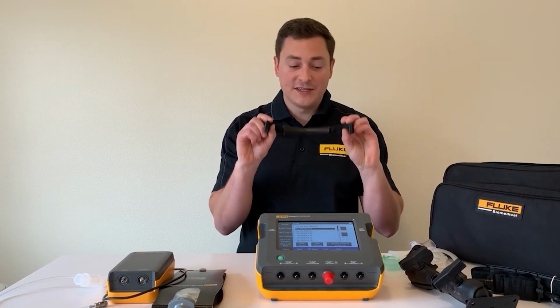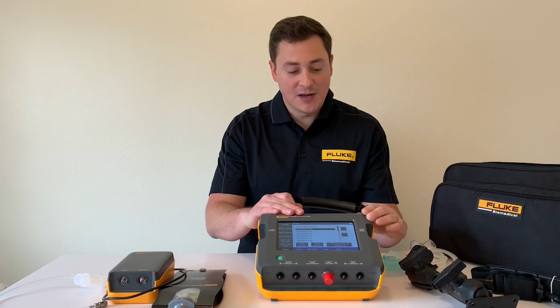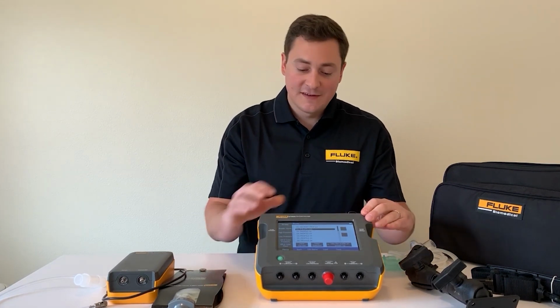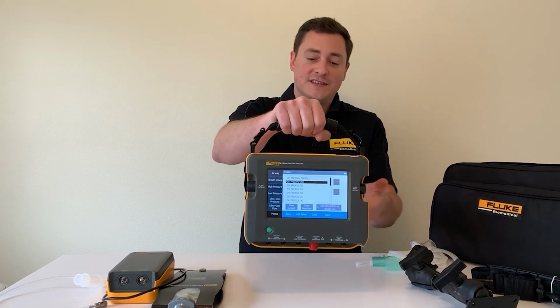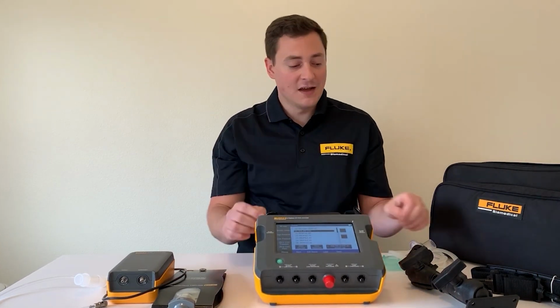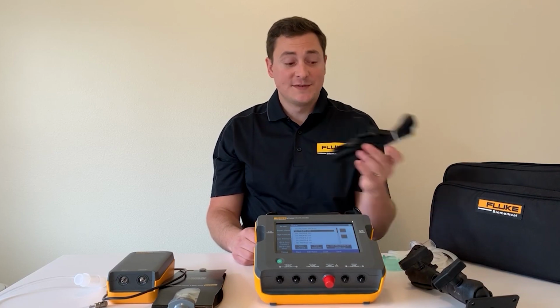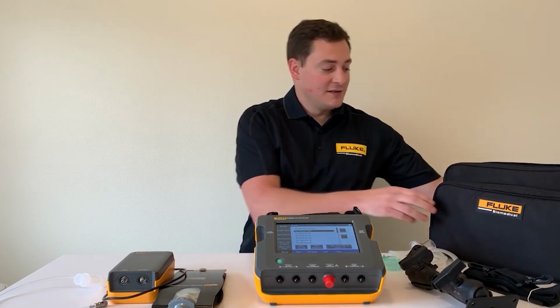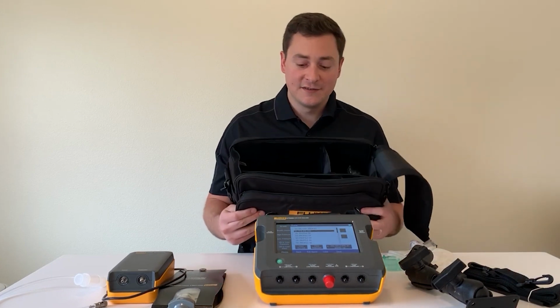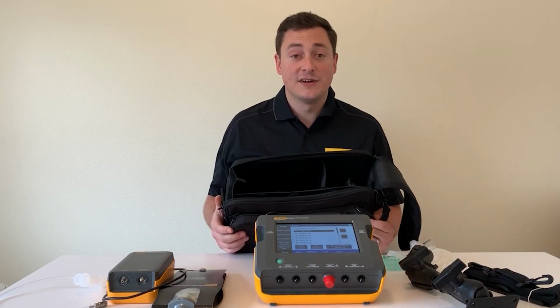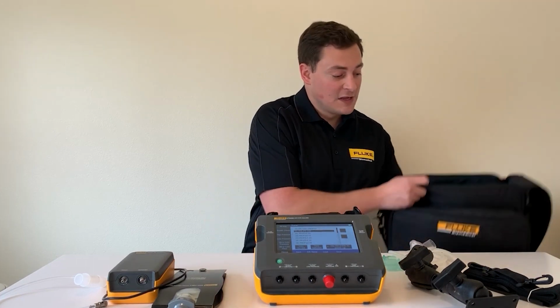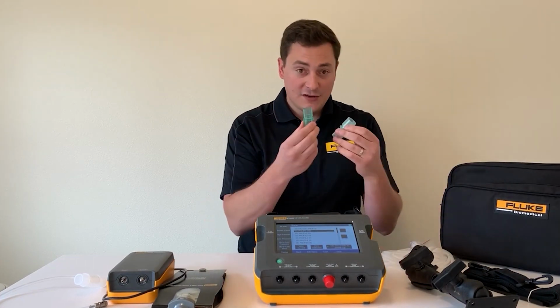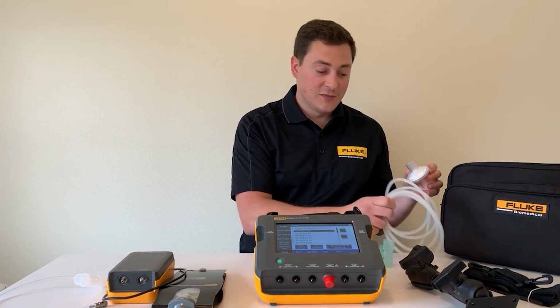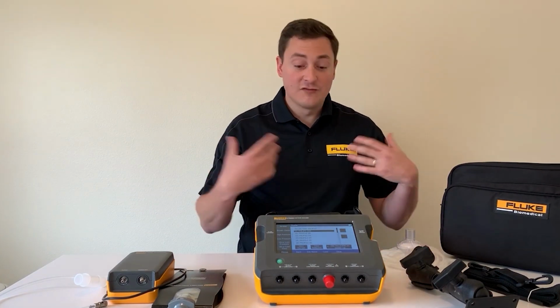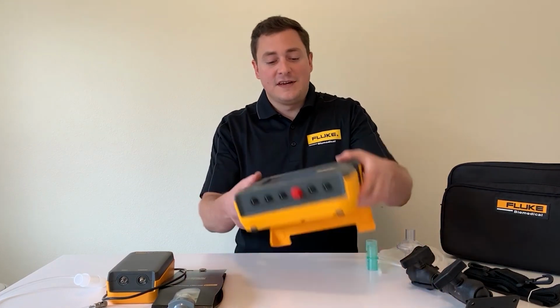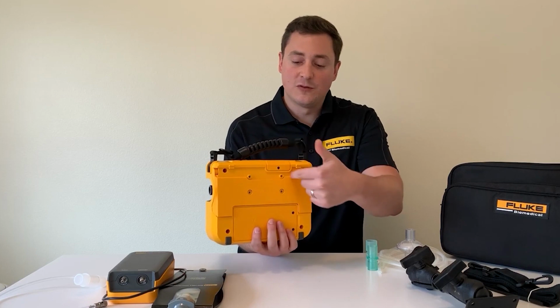So moving from place to place, we talked about those handles. These just pop right into the unit, right here on the back, and you can carry it around very easily because this unit does not weigh that much. It also integrates with some of the shoulder straps that are available with the unit. And again, you can put those shoulder straps on your case, which easily fits a VT and a vapor anesthesia tester in there, along with all your accessories. So you'll get your accessories to start. Again, you'll get your fittings, you'll get a filter, you'll get some tubing right in the unit, and you're ready to go, right? The other thing that I did not touch on were these 4 holes on the back.